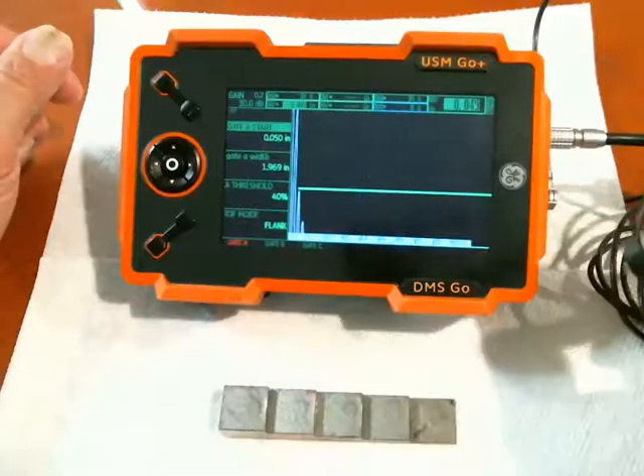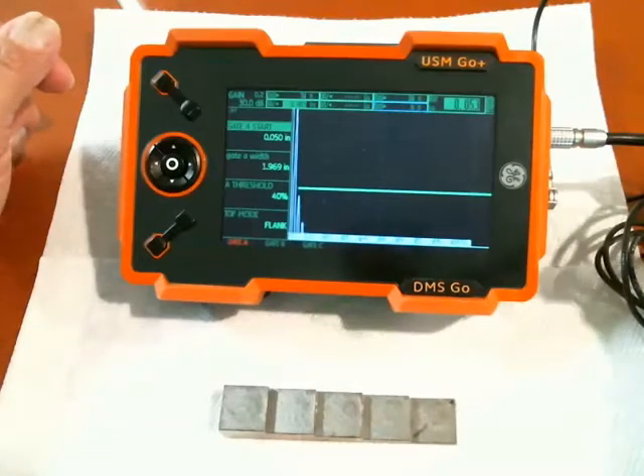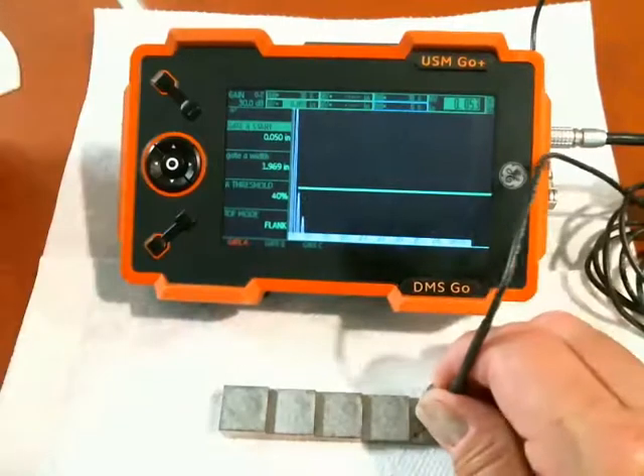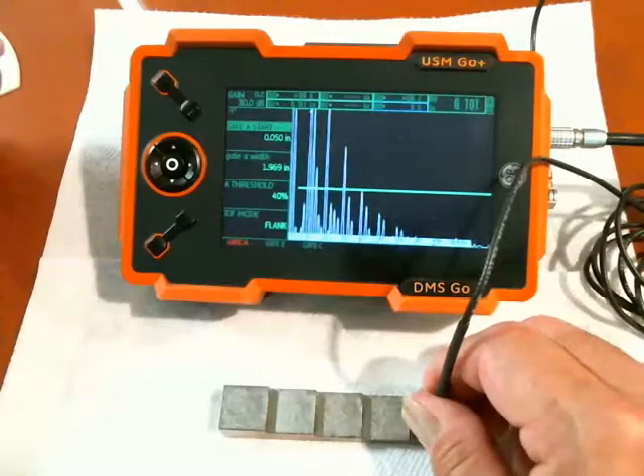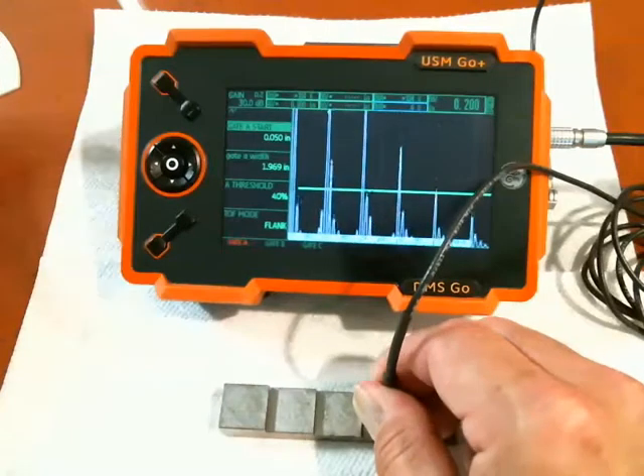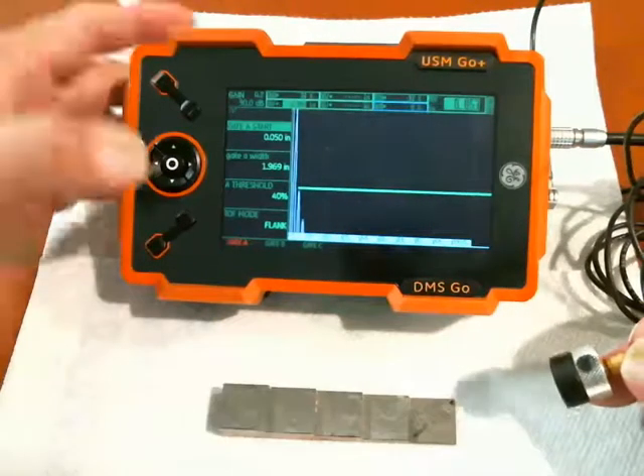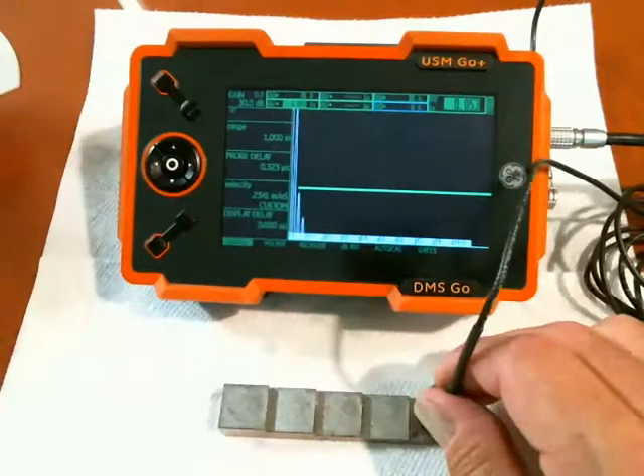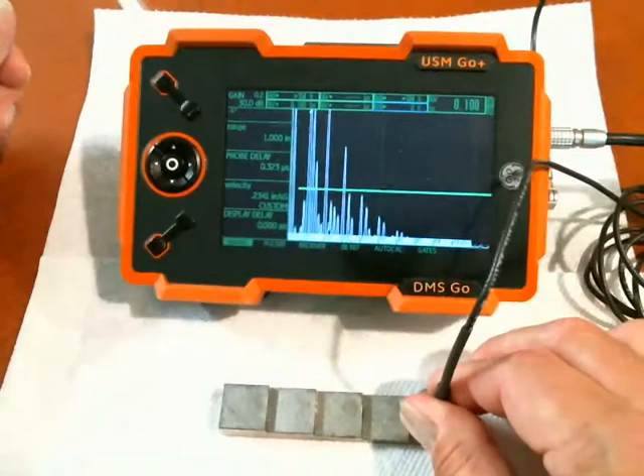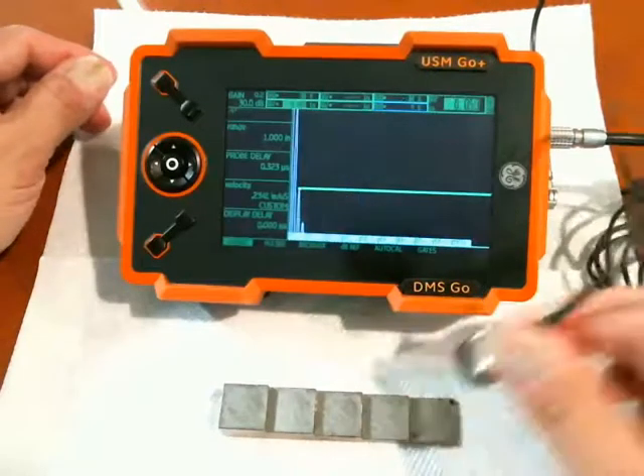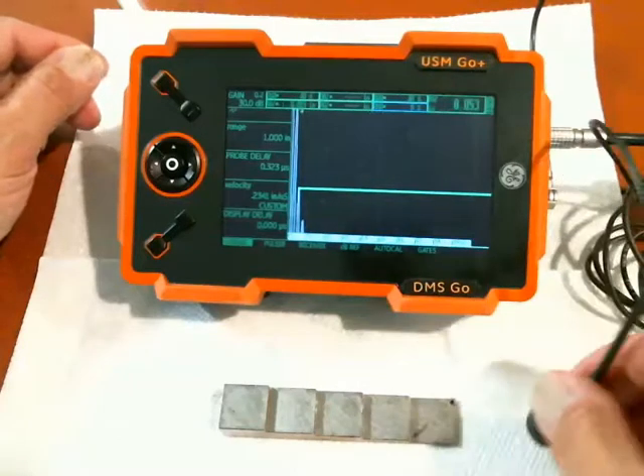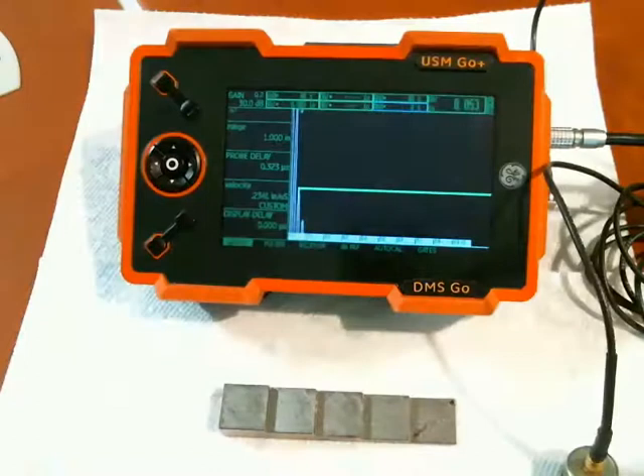So again, S-A — sound path in gate A — is the measurement we want to use. We want to set up gate A to be broken by the back wall echo. This technique works with a single or dual probe; you'll just have to set up for that single or dual mode in your receiver menu. Once you've selected sound path in A for your measurement, that's going to be your thickness measurement, and you can calibrate probe delay and velocity either manually or using the AutoCal feature. I'm Dan Groninger for GE Inspection Technologies — thank you very much for joining me.